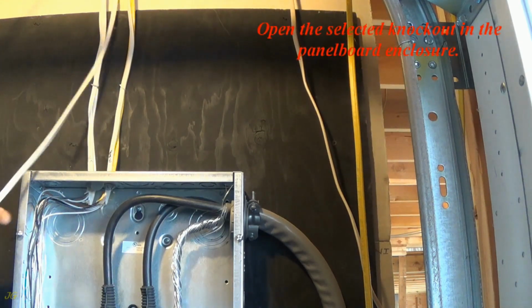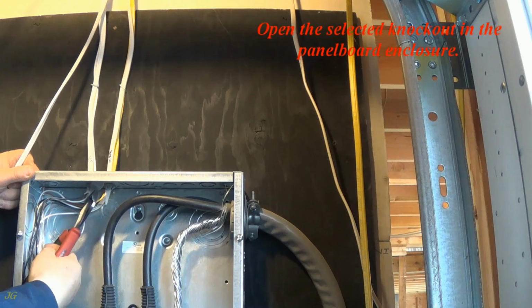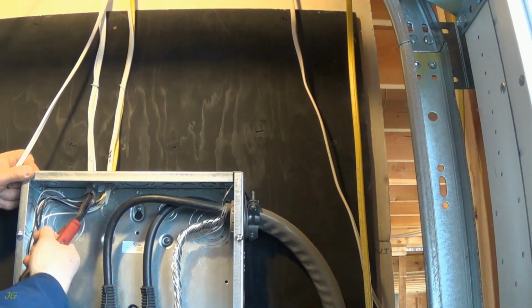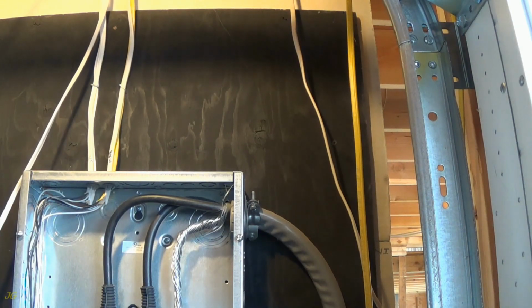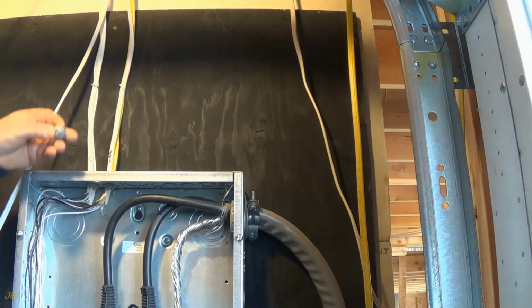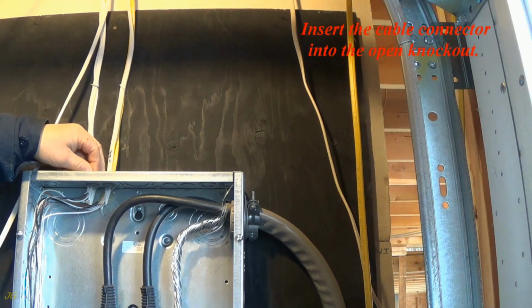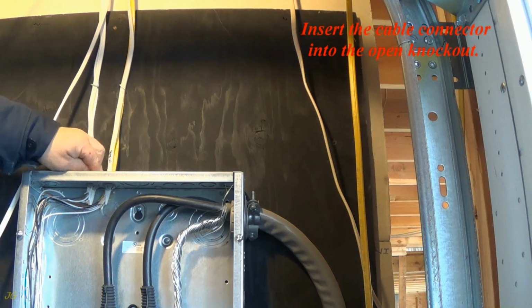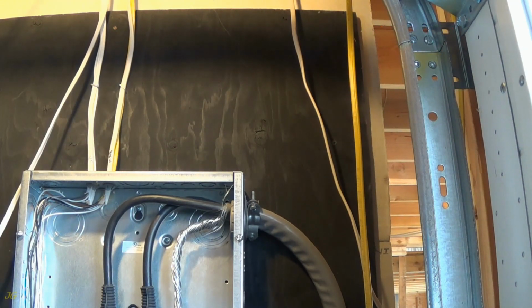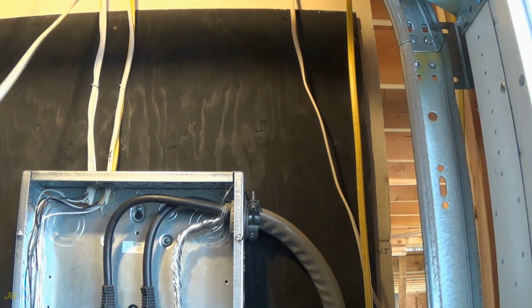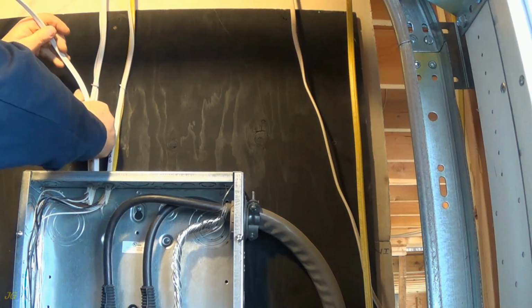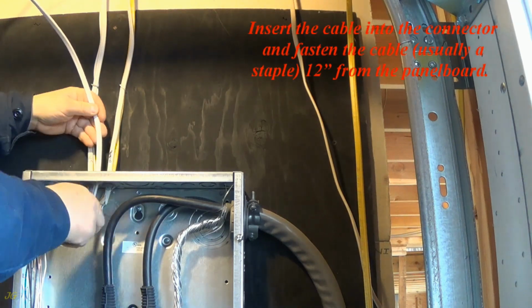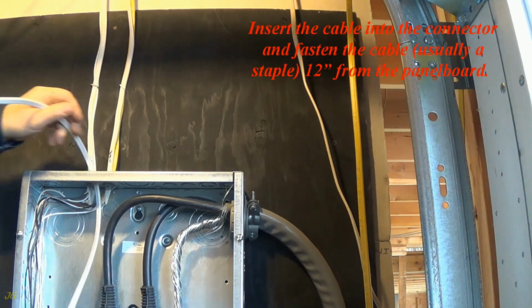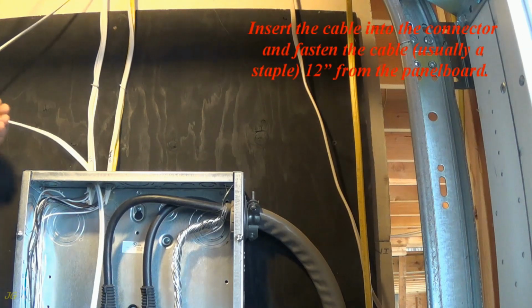Open the selected knockout in the panel board enclosure. Insert the cable connector into the open knockout. Insert the cable into the connector and fasten the cable, usually a staple, 12 inches from the panel board.